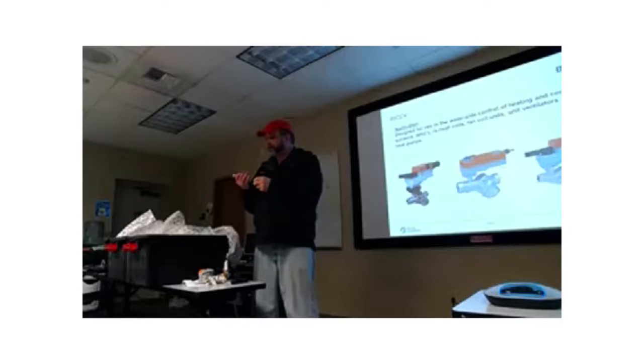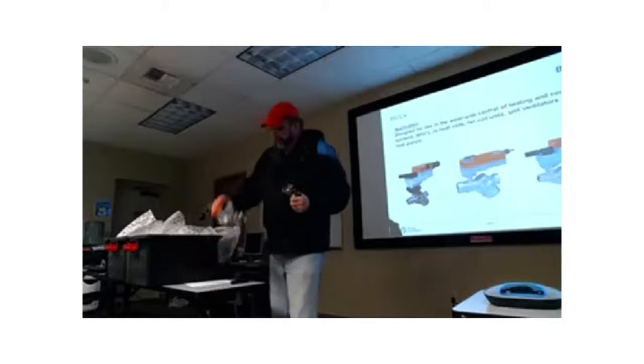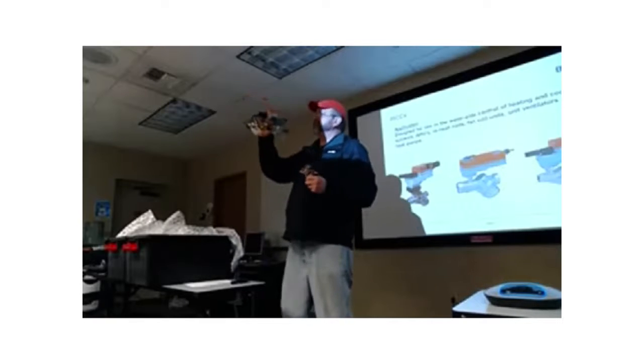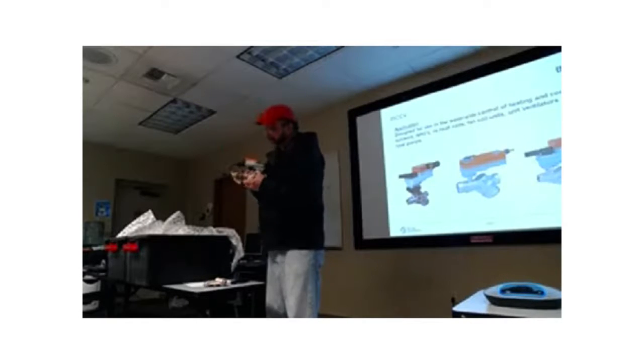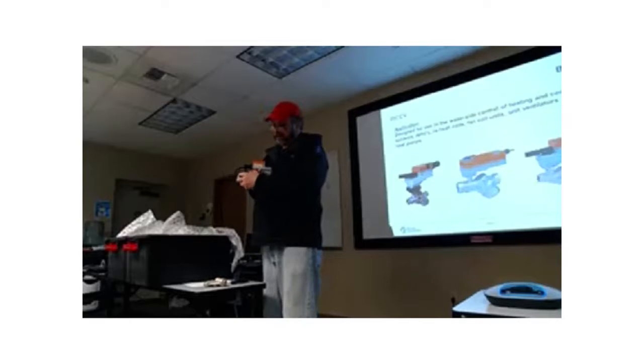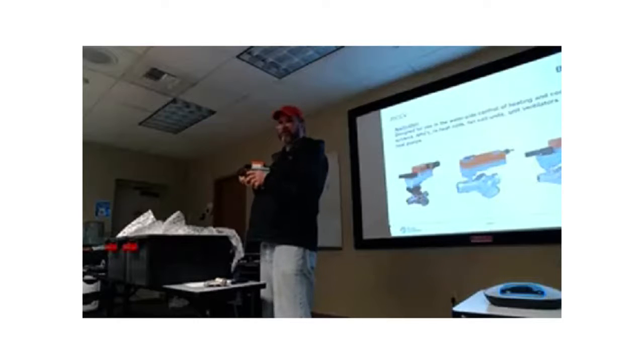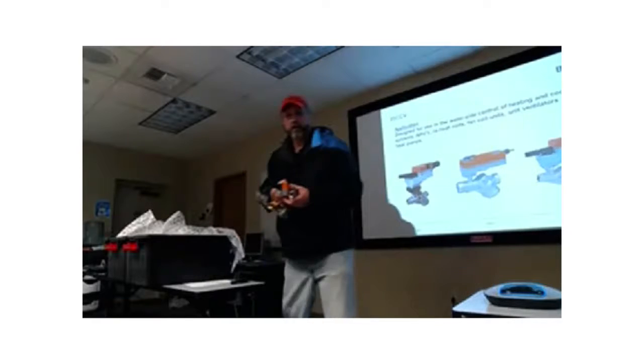We have many competitors now that have mechanical pressure independent valves. That's the way it works. This is an example of one with a non-spring return actuator on it. And this is actually a calibrated orifice, so if the balancer wanted to check the flow rate through it, he can measure across these taps and go to a chart and confirm the flow. So that's mechanical pressure independent.